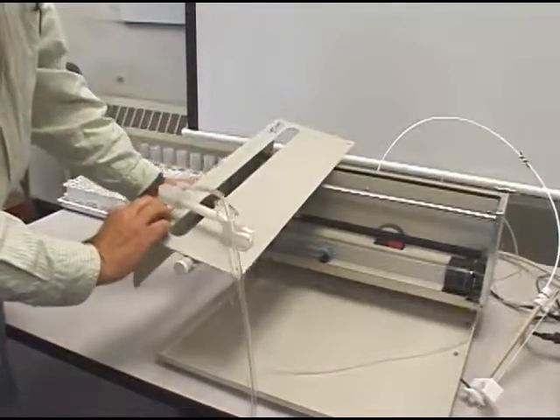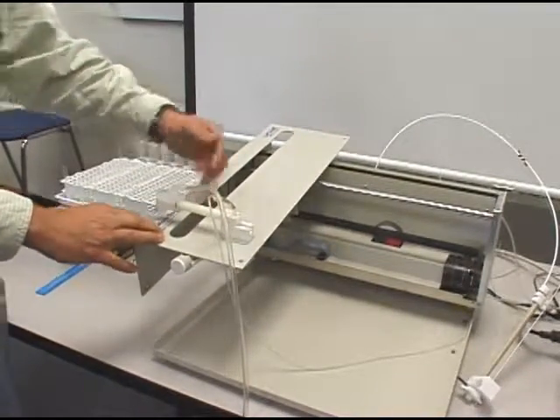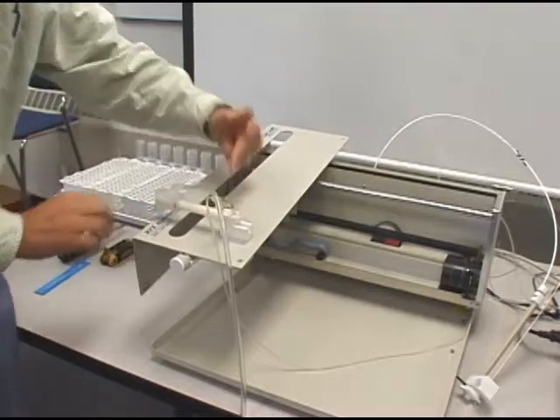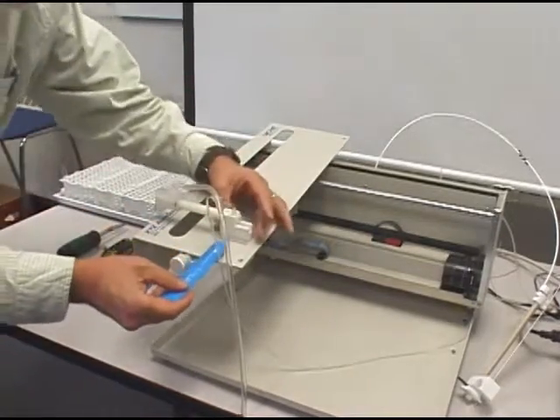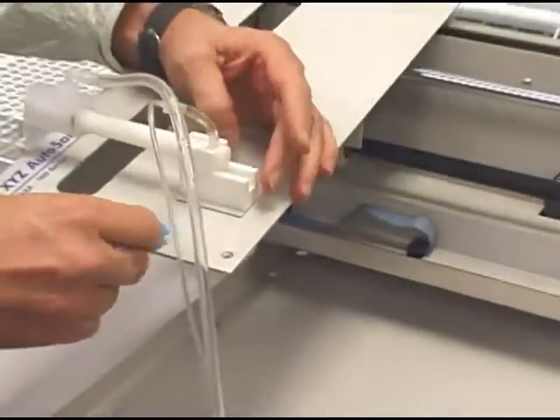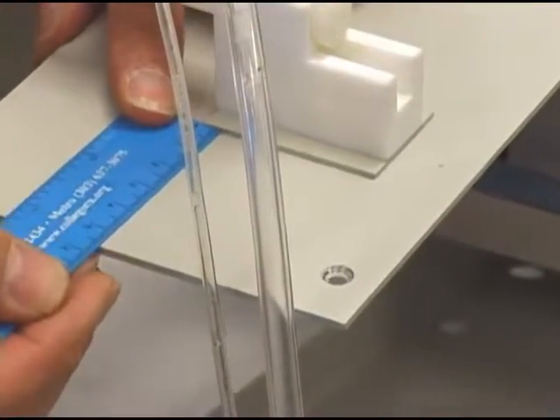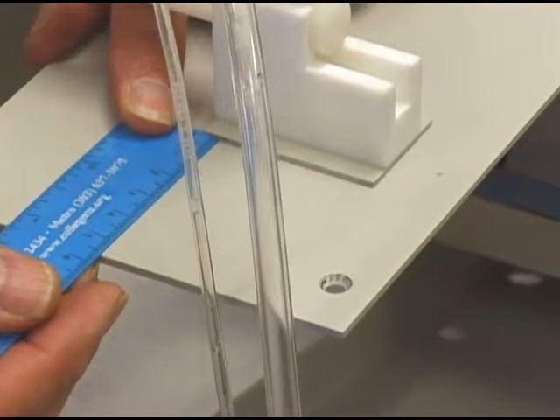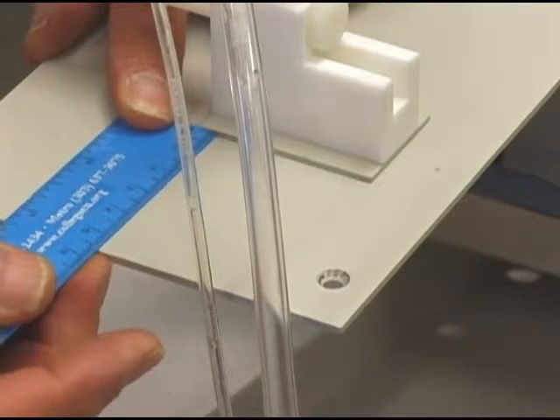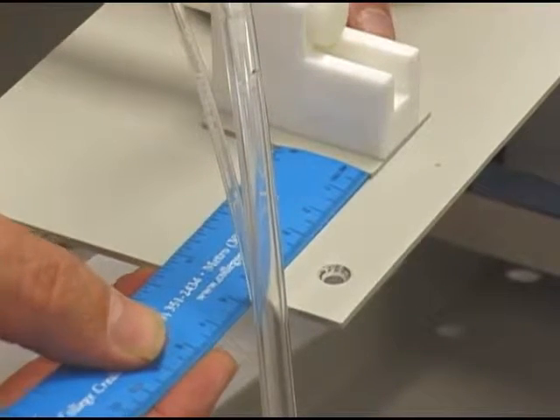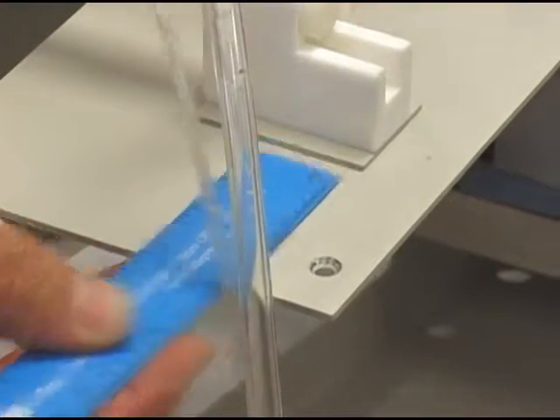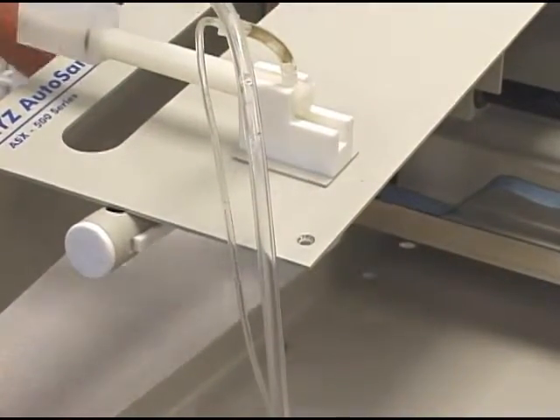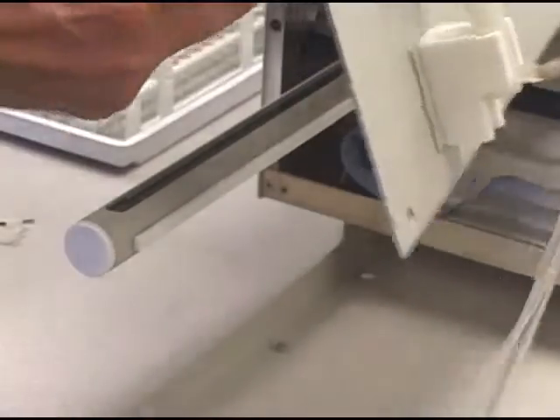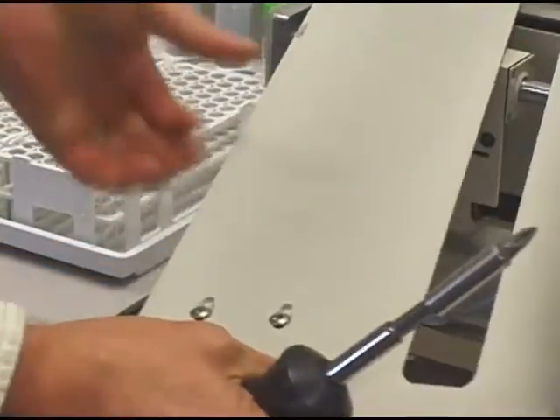Now I said I had to move this wash bath 4 millimeters in that direction. So I'll take my ruler and measure the top of this mount and see that it comes out to 5.5 centimeters or 55 millimeters from the edge at the top, and also 55 millimeters on the bottom. So I'll loosen those screws, and I've got to then move that wash bath over 4 millimeters. So it'll actually come to 51 millimeters.